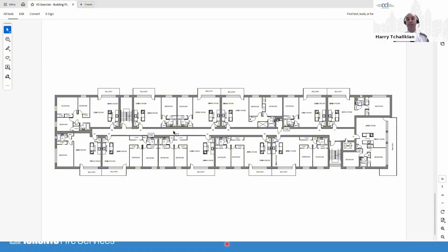If you have any doubt that that suction air, where that air originated, could someday potentially be transporting carbon monoxide, and typically it is meant for the failure of a heat exchanger or failure of the flue exhaust where a leak develops, or the furnace room is spreading carbon monoxide because of a ventilation issue, and then it goes subsequently to the bordering units, which was already addressed, and then you may have air from that service room blowing through the rest of the building. So unfortunately, I can't give you a one-size-fits-all answer because there is no one-size-fits-all answer, except to say, if in doubt, put the carbon monoxide alarms in.